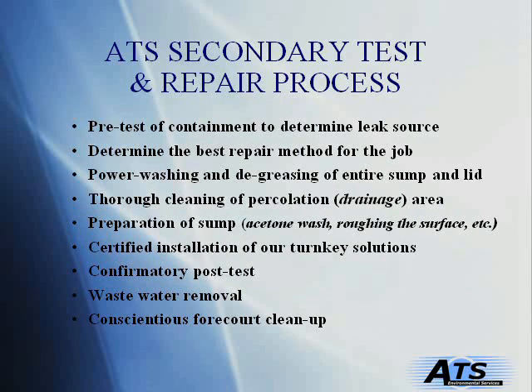Okay, so let's explain quickly ATS's secondary test and repair process. We start with a pre-test of the containment to determine the leak source. Then we'll be able to determine the best repair method for the job. We'll then power wash and degrease the entire sump and lid. We'll perform a thorough cleaning of the percolation area. We'll then prepare the sump, provide certified installation of our turnkey solutions, followed by a confirmatory test, wastewater removal, and a conscientious forecourt clean-up.